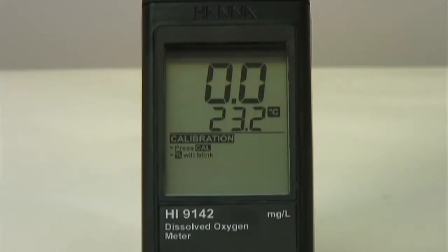Take note, while the connect probe message may disappear after only a couple of minutes, we actually recommend that you wait about 15 minutes for the probe to achieve polarization. This ensures that you have a properly polarized probe. Failure to do this will result in incorrect readings. Alright now, let's calibrate. This won't take long at all. There are really only 3 steps. Preparing your standard, performing a 0% calibration, and performing a 100% water-saturated air calibration.